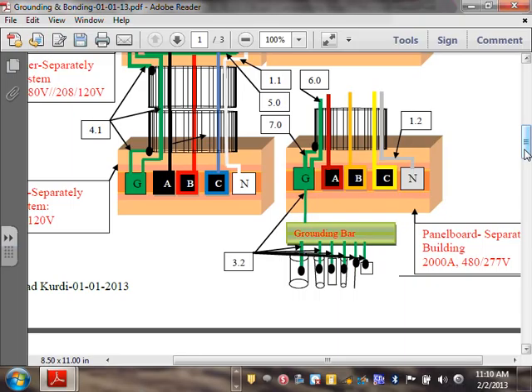But the challenge here is if you have a shield. Say you have a coaxial cable between the two buildings. Every time you enter a building with a coaxial cable, per chapter 8, you have to bond the shield at the point of entry, the demarcation point. So I bonded my coaxial cable at the first building. I entered another building, what do you need to do again? You bond it again. Now the coaxial cable shield is actually a neutral conductor, right? If you bond the neutral here, there will be current going through the shield. Now that would be a hazard. Does that make sense, guys? Why we don't bond the neutral again?